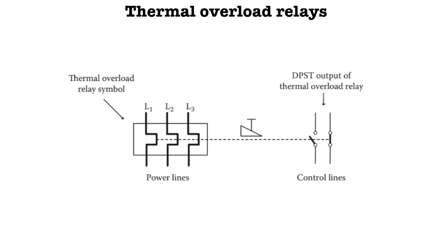At the heart of the thermal overload relay operation is the bimetallic strip, a component which is made of two metals with different thermal expansion properties. As the motor current increases, the strip heats up and bends, and if the motor current exceeds its nominal value for an extended period, the bending strip triggers a mechanism that deactivates the power relay, thereby stopping the motor to prevent further damage to the system.